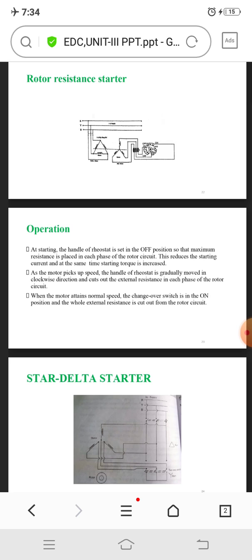One of the benefits with this starting method is the possibility to adjust the torque to the exact need, whether the application is loaded or not. In principle, the full starting torque is available, but with the big difference that the starting procedure is much more forgiving to the driven machinery, with lower maintenance cost as a result. Another feature of the soft starter is the soft stop function, which is very useful when stopping pumps where the problem is water hammering in the pipe system. A direct stop is for star delta starter and a direct online starter. The soft stop function can also be used when stopping conveyor belts to prevent material from damage when the belt stops too quickly.